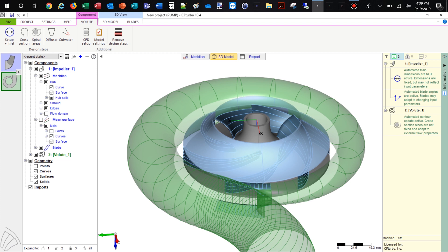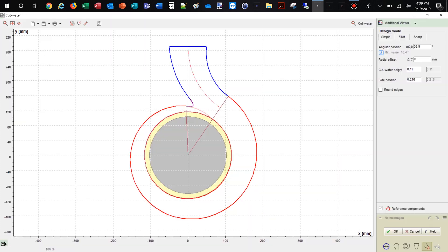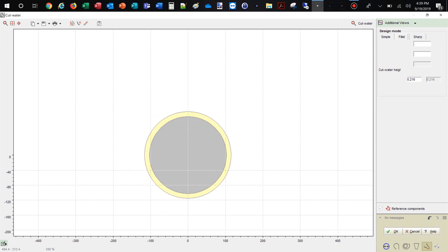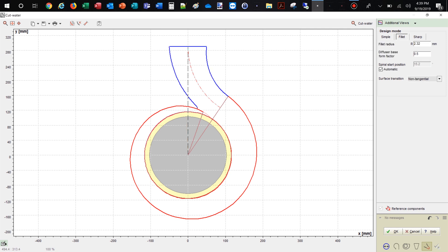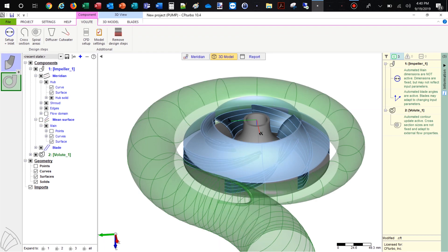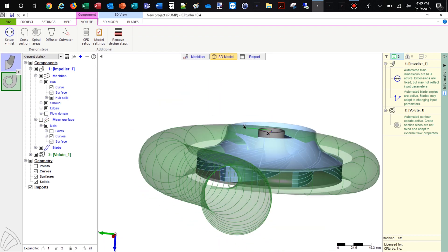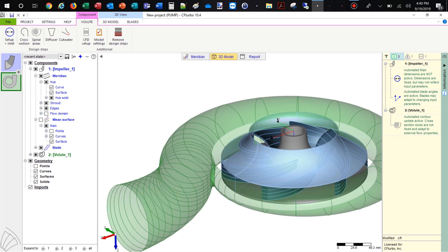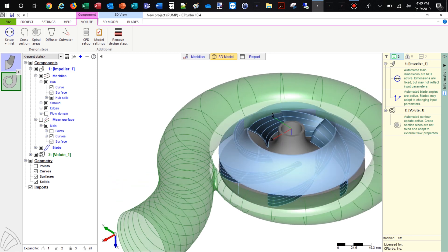For the cut water, we create a fillet radius instead of the default simple cut water design. We can modify the radius and the spiral start position. Another possibility for creating the cut water design would be to create a sharp intersection between the volute and the diffuser. The shape of the cut water will be automatically updated in our 3D viewer.